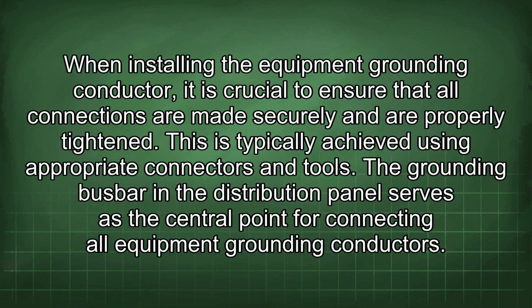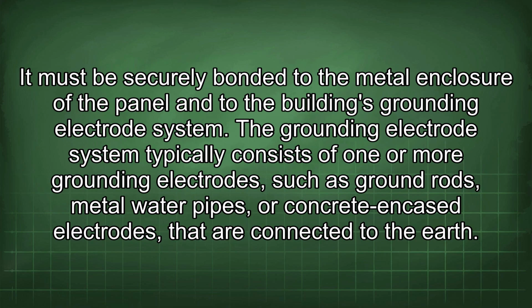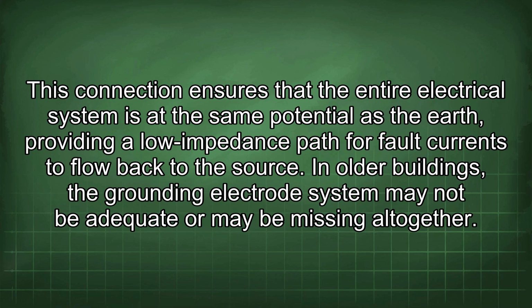When installing the equipment grounding conductor, it is crucial to ensure that all connections are made securely and are properly tightened. This is typically achieved using appropriate connectors and tools. The grounding busbar in the distribution panel serves as a central point for connecting all equipment grounding conductors. It must be securely bonded to the metal enclosure of the panel and to the building's grounding electrode system. The grounding electrode system typically consists of one or more grounding electrodes, such as ground rods, metal water pipes, or concrete encased electrodes that are connected to the earth. This connection ensures that the entire electrical system is at the same potential as the earth, providing a low impedance path for fault currents to flow back to the source.